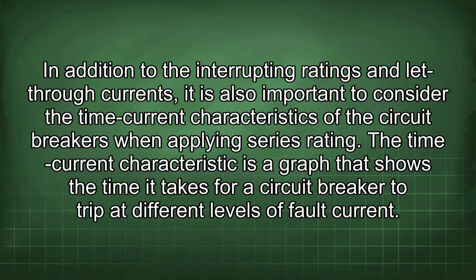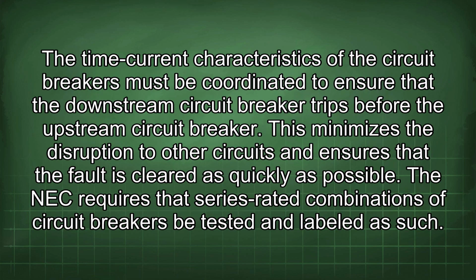The time current characteristic is a graph that shows the time it takes for a circuit breaker to trip at different levels of fault current. The time current characteristics of the circuit breakers must be coordinated to ensure that the downstream circuit breaker trips before the upstream circuit breaker. This minimizes the disruption to other circuits and ensures that the fault is cleared as quickly as possible. The NEC requires that series-rated combinations of circuit breakers be tested and labeled as such.